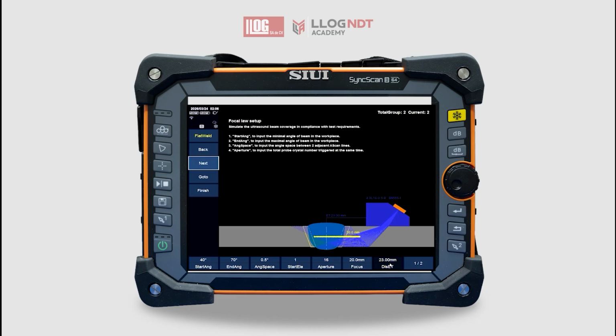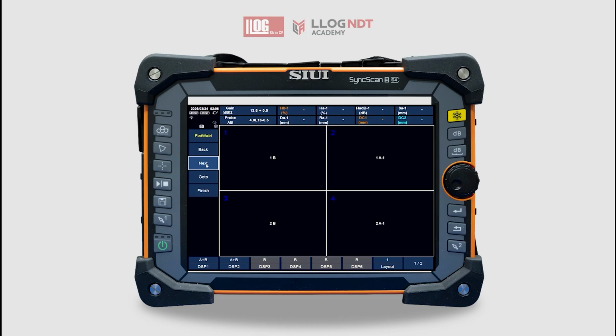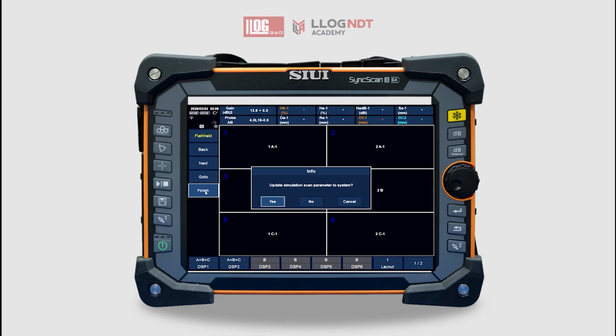Adjust the ET offset to 22 millimeters to cover the remaining half of the weld. Select group 1 of 2 to adjust the focal depth, then enable both groups to display them on screen. Press Next. Finally, configure the scan layout to A plus B plus C for both groups. Press Finish and confirm the parameter update in the system simulation.